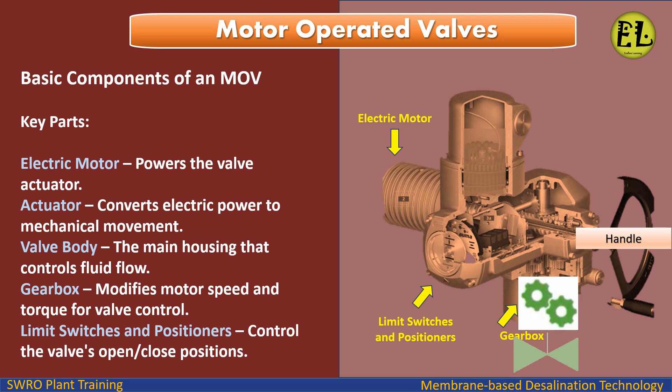Basic components of an MOV include: the Electric Motor, which powers the valve actuator; the Actuator, which converts electric power to mechanical movement; the Valve Body, which is the main housing that controls fluid flow; and the Gearbox, which modifies motor speed and torque for valve control.